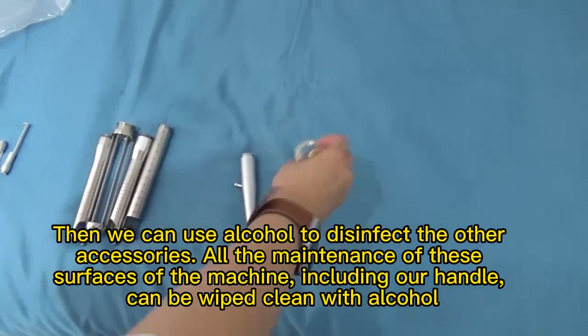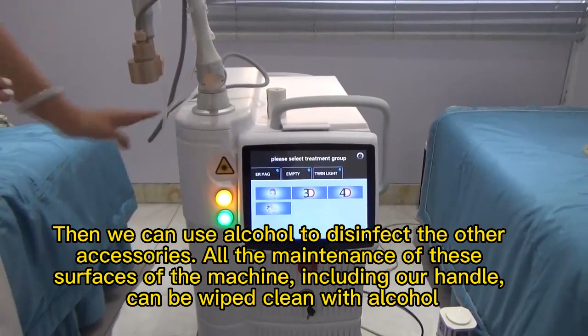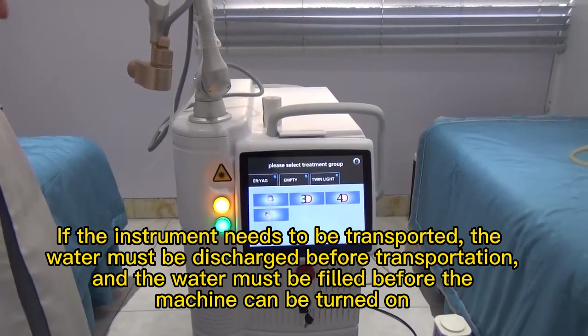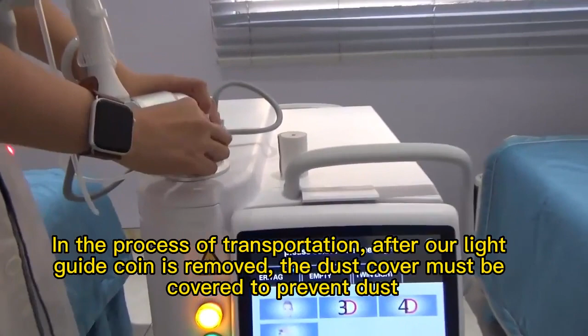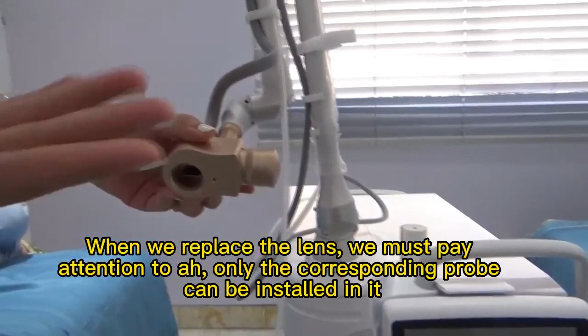All the maintenance of these surfaces of the machine, including our handle, can be wiped clean with alcohol. And then the water in our machine is required to be changed once a month, and must be either distilled water or pure water. If the instrument needs to be transported, the water must be discharged before transportation, and the water must be filled before the machine can be turned on. In the process of transportation, after our light guide coil is removed, the dust cover must be covered to prevent dust.